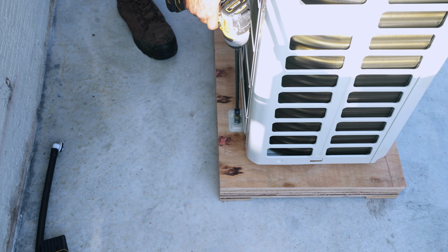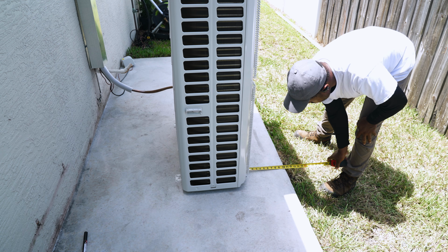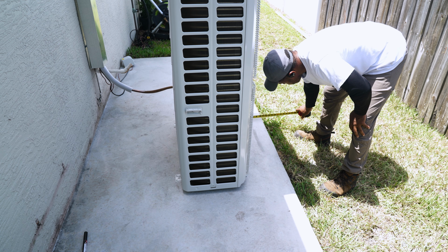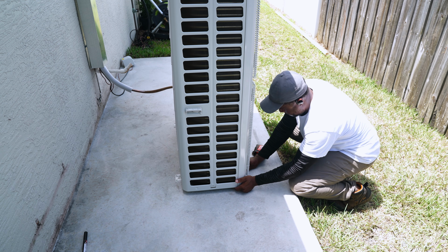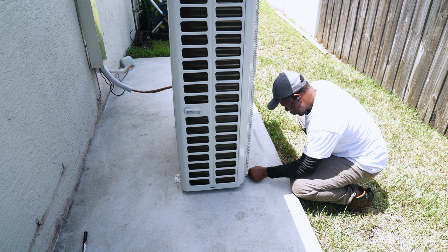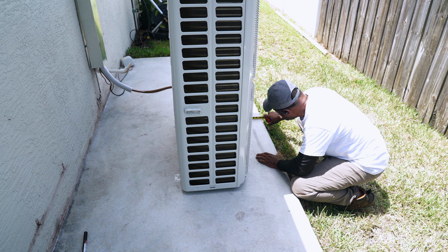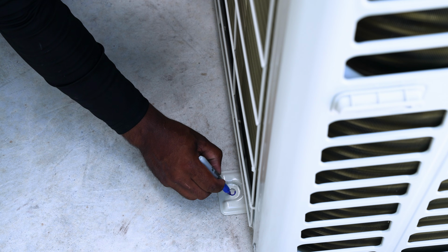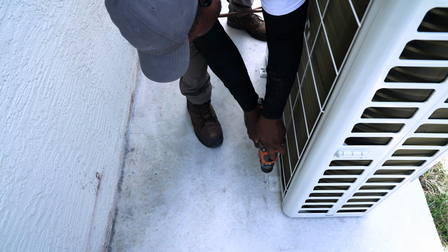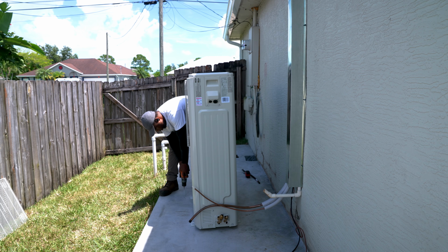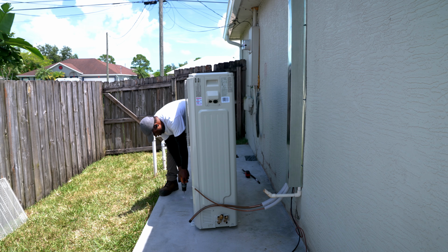The unit is slim and it's designed to take up less space. If needed, the unit can be mounted as little as 12 inches away from the wall. That's not a big concern for me, so I left myself plenty of room so I can do work behind the unit. I'll align the unit to the front of the slab, then I'll mark the mounting holes. And after, I'll use a masonry bit to drill the holes into the slab.